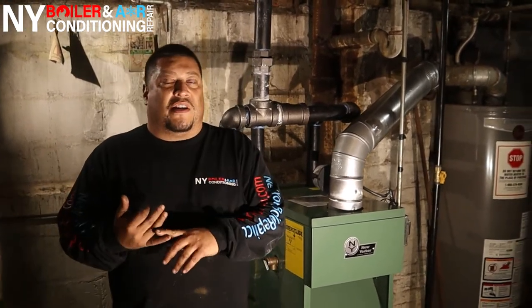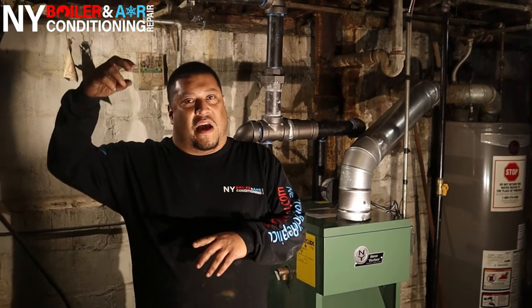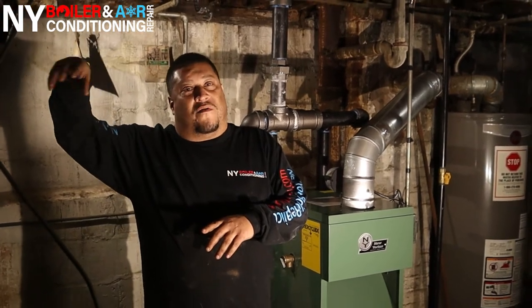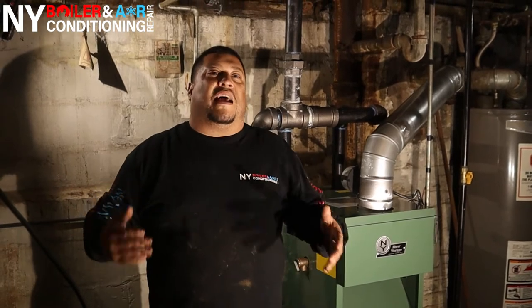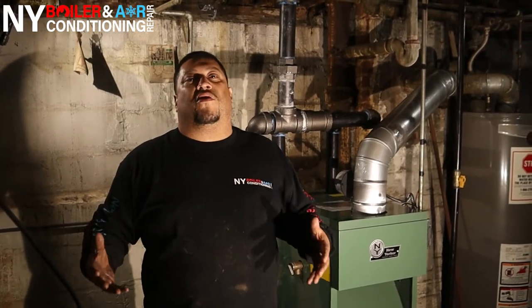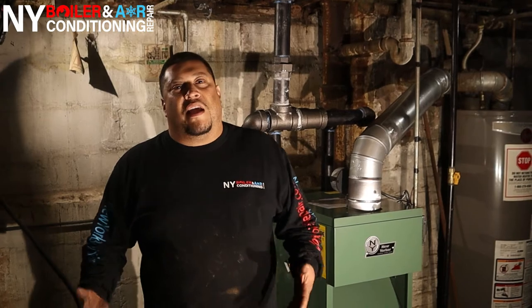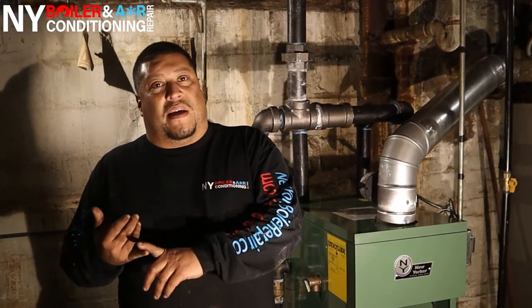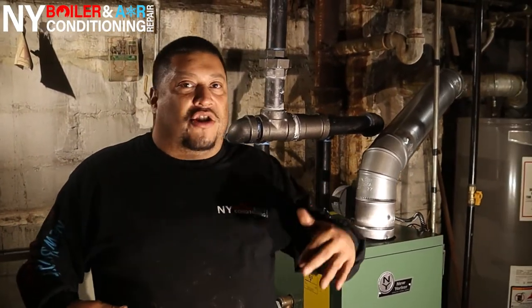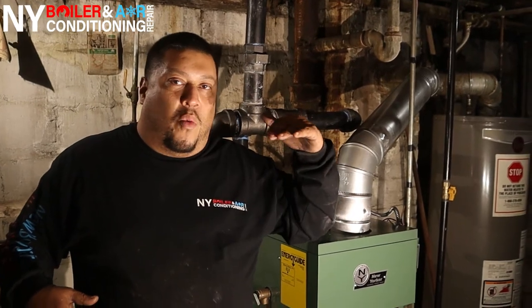We gotta check the air vents, the vent risers, usually at the tail end of the risers, and also check your return. A lot of times people don't realize those return lines have been there for years and are clogged with sediment. That doesn't let it make the cycle, so it takes longer to make heat or steam, and you'll get knocking, banging, and surging in the water.